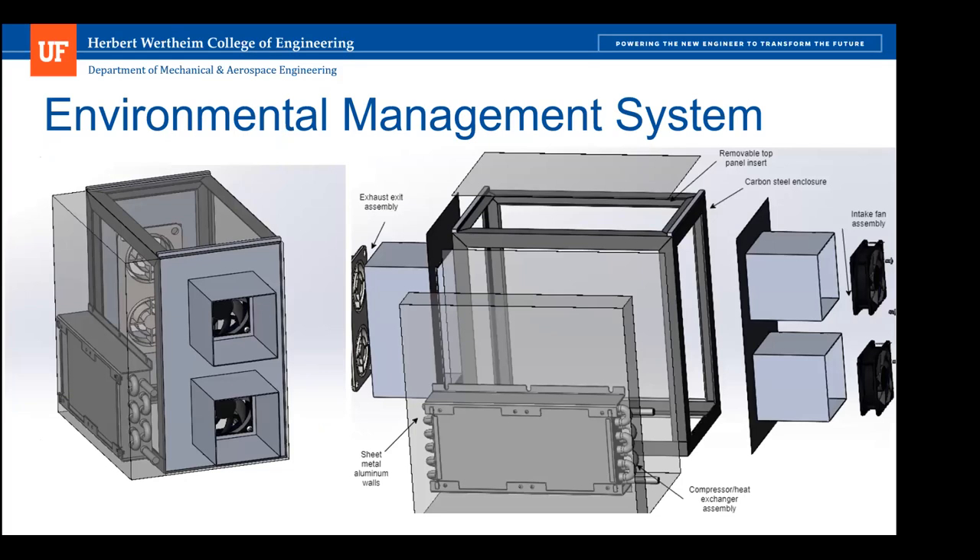The environmental management subsystem can be conceptualized as a contained closed loop system, which should not produce any condensation or release heat within the enclosed space of the bioreactor, which has delicate and sensitive electrical components. Comparable systems use a refrigerant or heating mechanism contained within an enclosed space, such as a PC tower or an actual fridge. The refrigerant approximation will circulate Freon R134a, which will alter the pressure of air within the condenser to promote the overall transfer of heat.